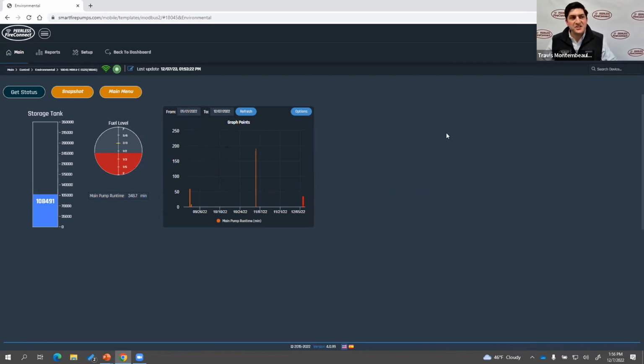So when you say estimate, I'm guessing you're talking about estimated flow? Yes, estimated flow. The only challenge with estimated flow on a variable speed pump is that we're losing that RPM component. We're not running at a fixed speed, so the calculation for estimated flow itself is off.